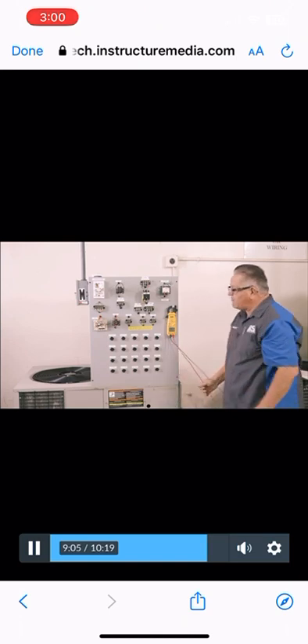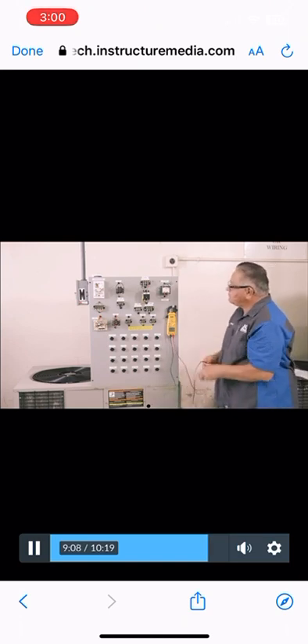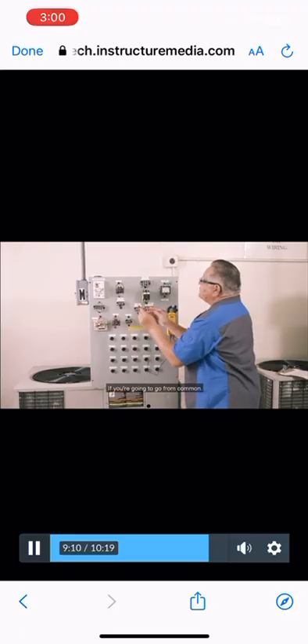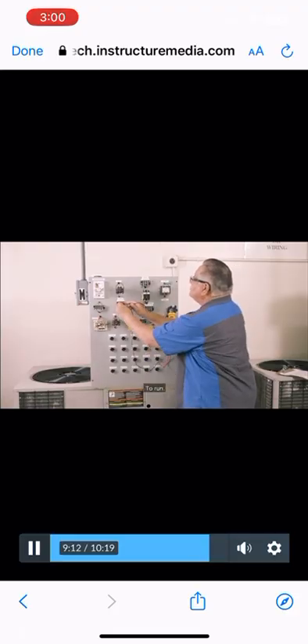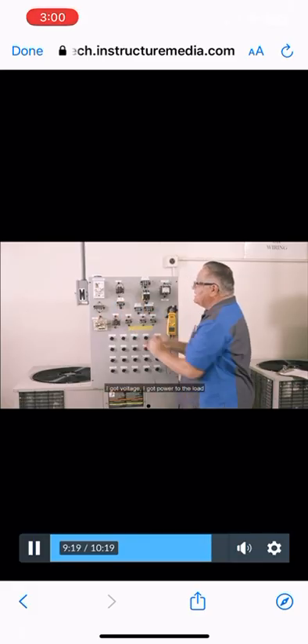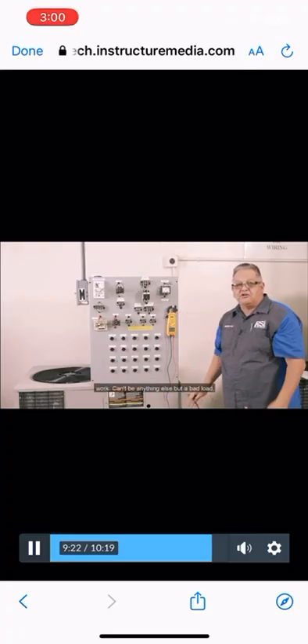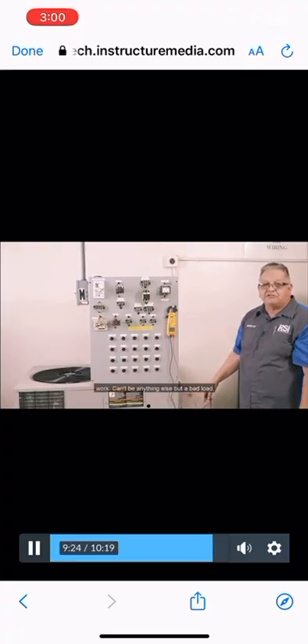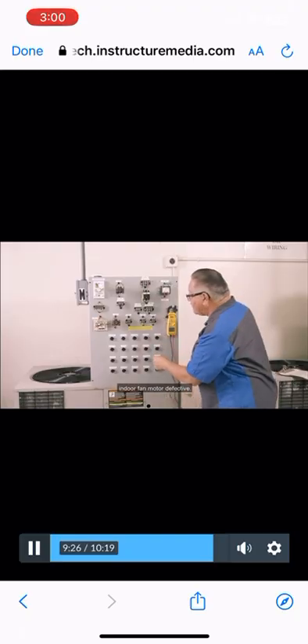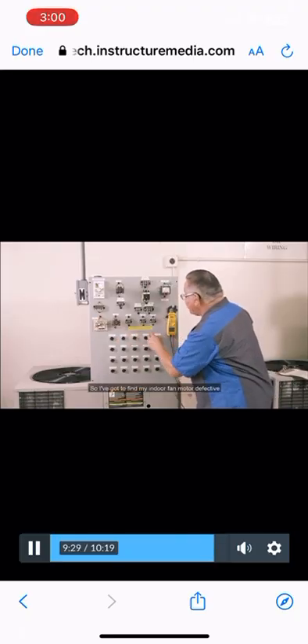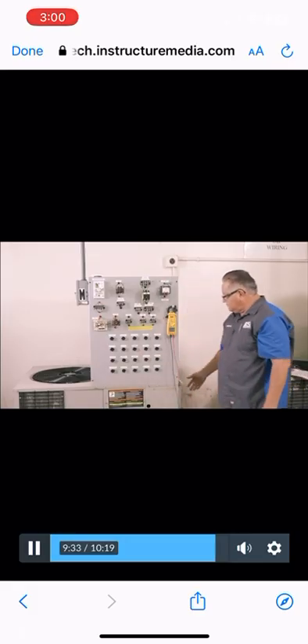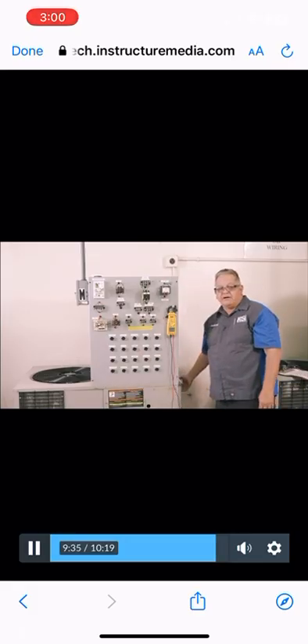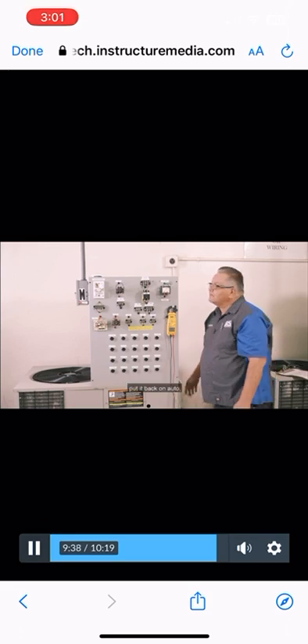So I go straight to my motor. IFM. You're going to go from common to run. And I got voltage. You're going to go common to start. I got voltage. I got power to the load. The load don't work. It can't be anything else but a bad load. Indoor fan motor defective. So I got to find my indoor fan motor defective right here. Indoor fan just came on. Put it back on auto.